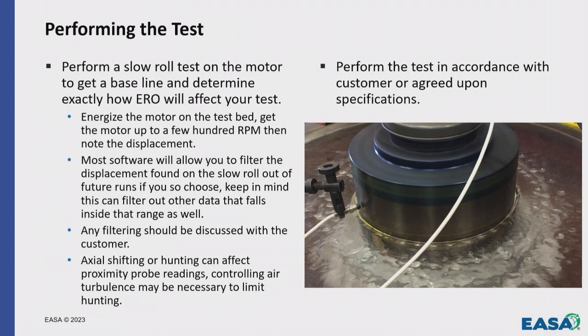The other thing to really look for is axial shifting or hunting. Happens a lot, especially in higher speed machines. You may need to block some vents or something of that nature to stop the hunting. If your machine's hunting, that's going to affect your Prox Probe readings as well. So I typically find I have to partially block off the airflow, which doesn't hurt anything. The motor's not under load, it'll be fine. But if you can't get it and you notice that shaft just won't quit hunting, try blocking off your airflow. You get a lot of turbulence in there, and that will help.